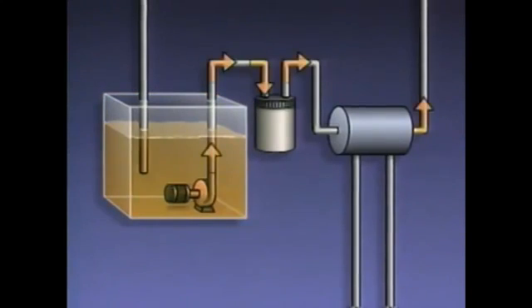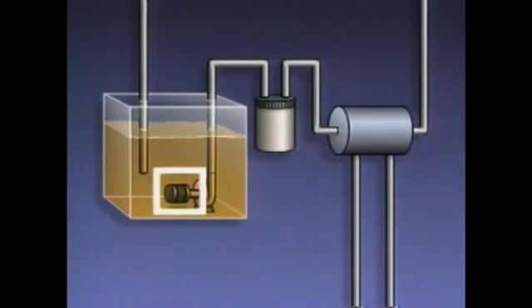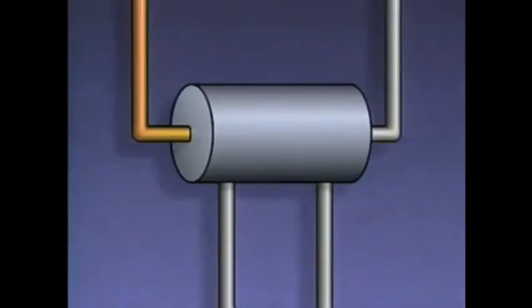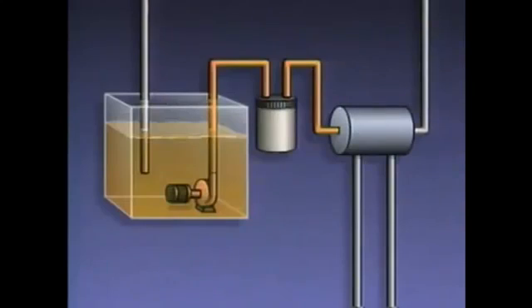During operation, the pump draws oil out of the reservoir and moves it through the rest of the system. A screen on the pump traps large solid particles and debris. From the pump, the oil goes through the oil filter, where dirt and other smaller particles are removed. If these materials are not removed, they can get into the compressor's moving parts and cause damage. From the filter, the clean oil flows to the oil cooler, which is a small heat exchanger. If the oil is allowed to overheat, it breaks down and loses its ability to lubricate, so cooling the oil prevents this from happening. The oil then flows to the compressor, where it lubricates bearings or other moving parts, and then flows back to the reservoir.